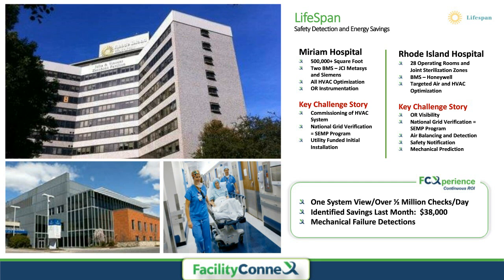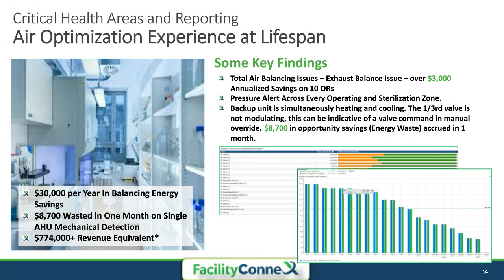Let me give you a bit of the air optimization story. This is one where we've had some balancing issues, and just over this last month, we saw over $3,000 in annualized savings in 10 ORs by helping them maintain that balance. They weren't off balance before—they started to get imbalanced as different things changed in the summer environment, because as you walk through the seasons, outside air temperatures and economizers start kicking in into the fall, so you tend to see different aspects of the system.